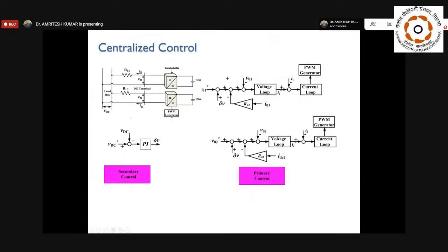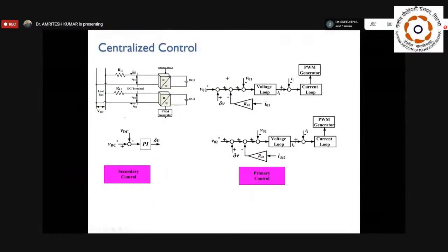Okay, so if you see the centralized control again, here you can see the same converters, parallel converters, are being connected. The secondary controller is basically comparing the actual voltage with the reference voltage of the DC bus that you want to maintain. This gives an error in voltage, and that error voltage is added with the reference voltage. As you know, we were maintaining this V01 as 250 volt, and we were not using this initially.